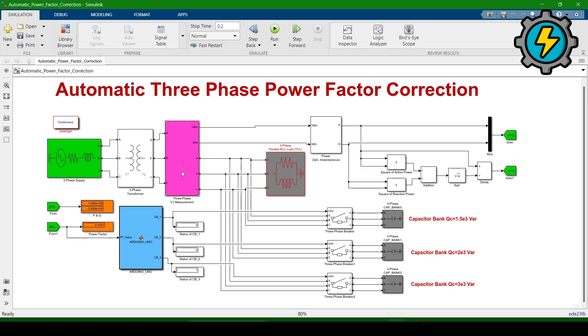Here is the three-phase transformer and this is the three-phase voltage and current measurement. From this measurement we are getting active power and reactive power, and then we are calculating the power factor. We square the active power, square the reactive power, add both, take the square root, then divide the active power by apparent power to get the power factor. This power factor will be shown in the display, along with reactive power and active power.